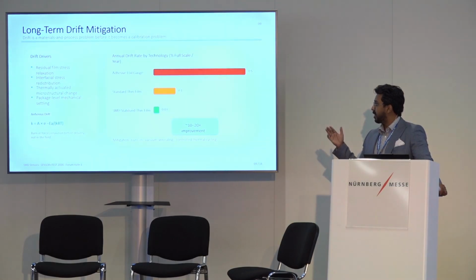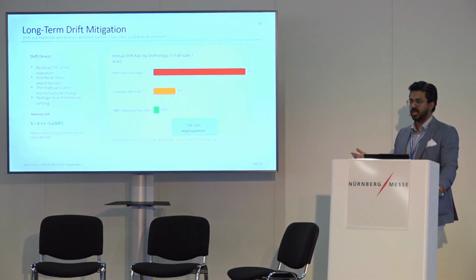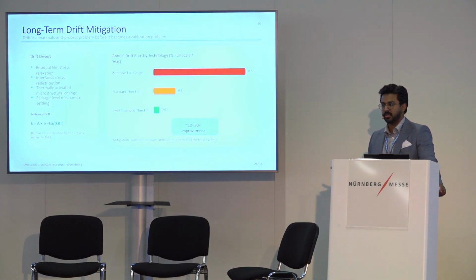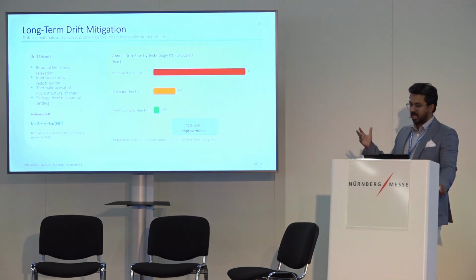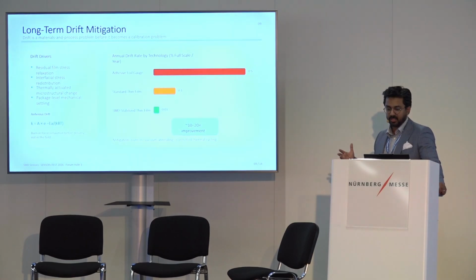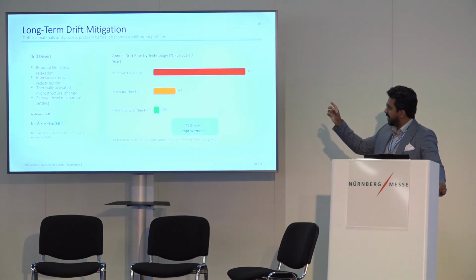So if we don't figure out that these drifts happen, we don't necessarily know over the long term. After 2 years, you won't see the drift. And if you are expecting a sensor to perform for 30 years and 2 years in it's starting to drop on results, you wouldn't be able to figure it out and condition monitor for a very long time. So we have to look into these elements, and we do this. We check the Arrhenius equation, which explains the trick.